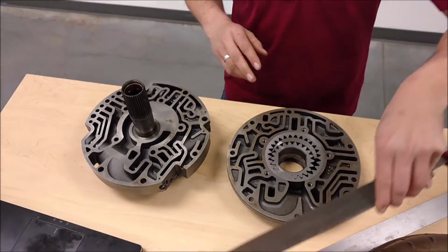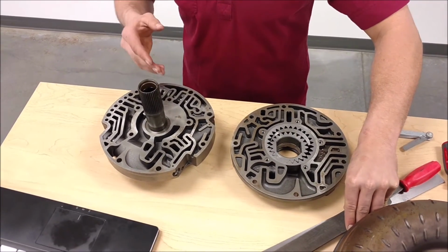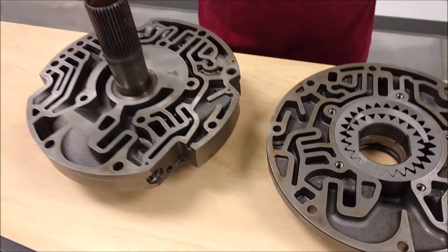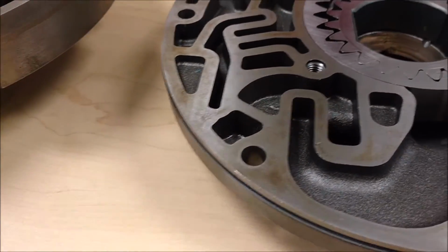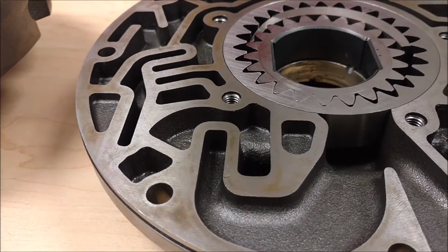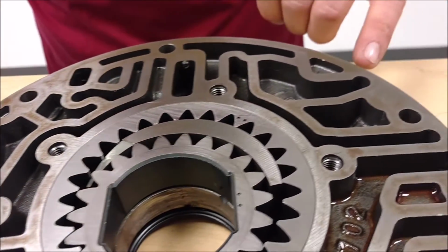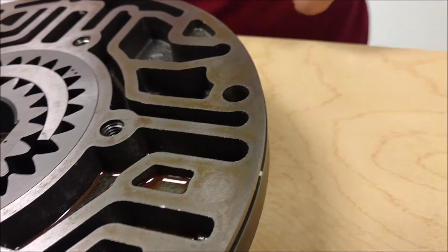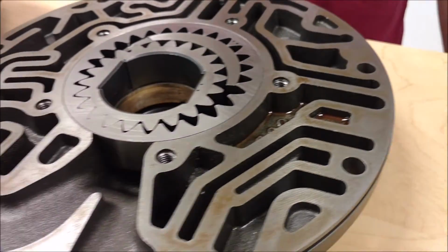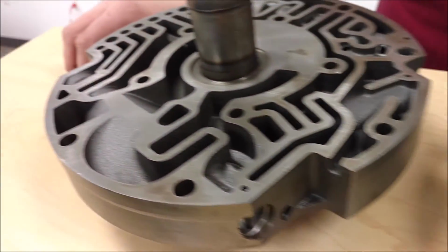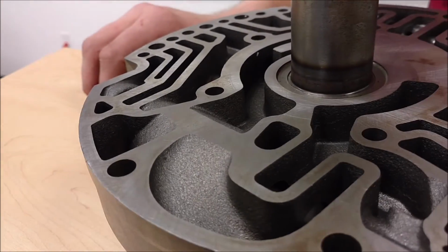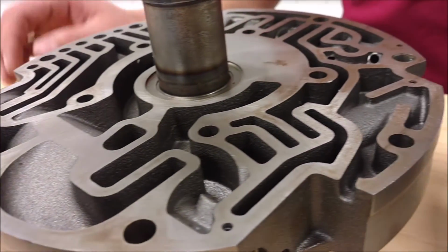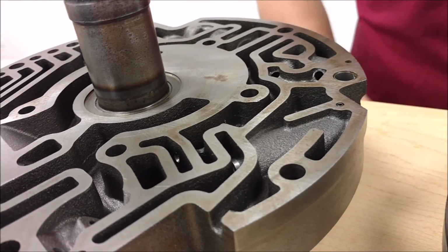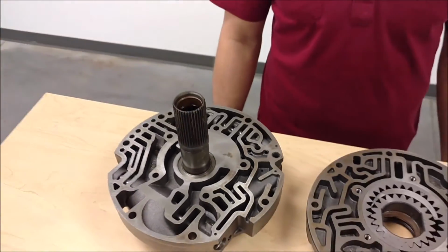Now what this does is if you see any shiny areas, this would mean that there is a high spot. On this pump, it looks pretty clean. You can see a few areas along the edges where it's a little bit shiny, but this pump is okay. If you have major areas where it's shiny, where when you were filing you felt like it was harder to push the file, this could indicate a warped pump.